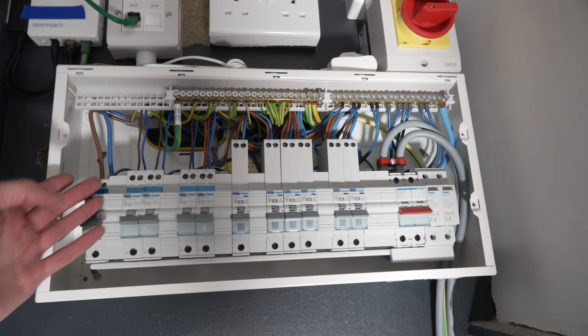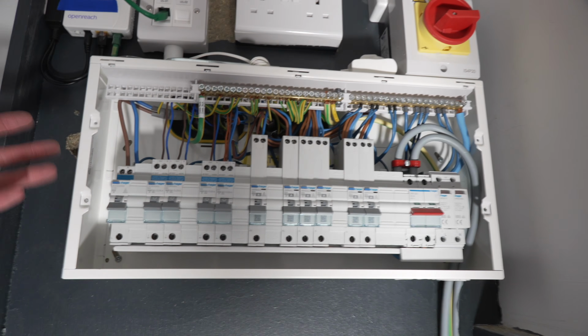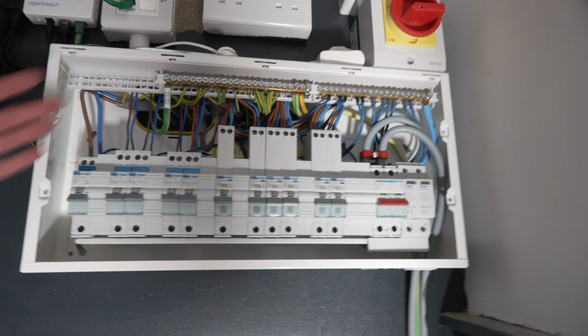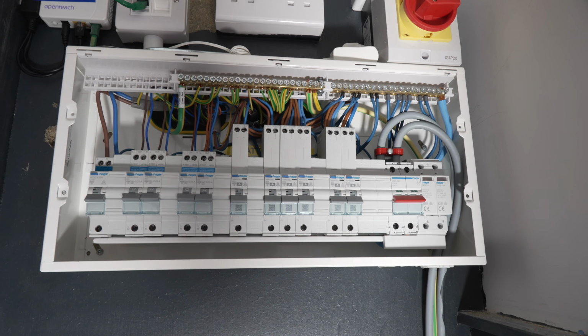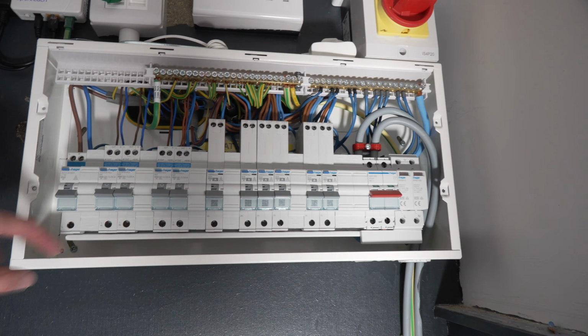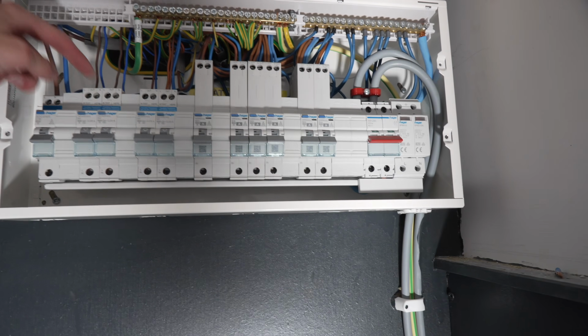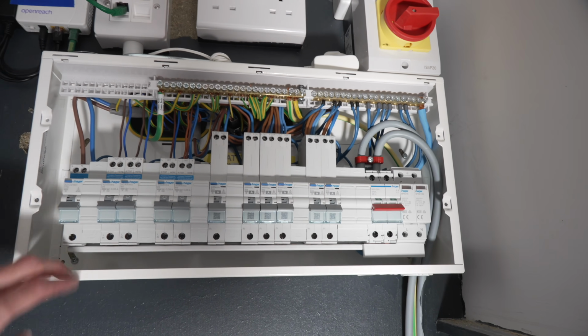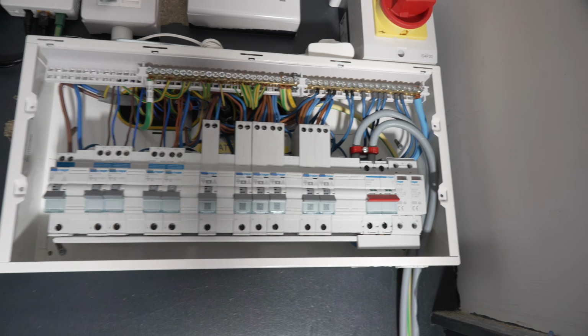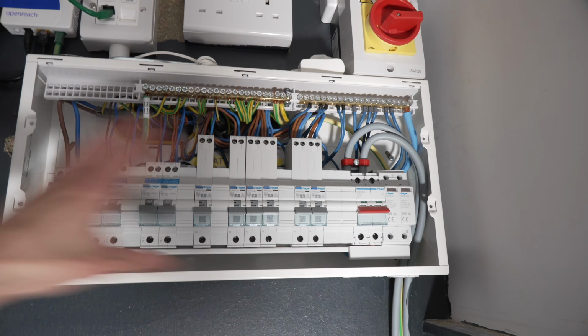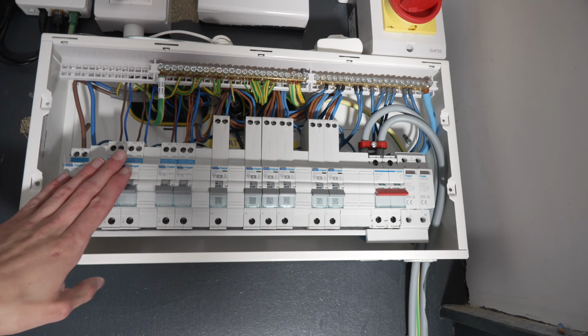And yes, you're not really technically adjusting any live wires in this job, you're just clipping CTs around them, but don't risk it. You're putting your hands into a board, there are little ends of the bus bar that can be live, there can be bits of copper sticking out of things, a wire could be loose and come out of a terminal. Don't risk it, fully isolate everything. So everything's now fully isolated and locked off, it's now ready to install.